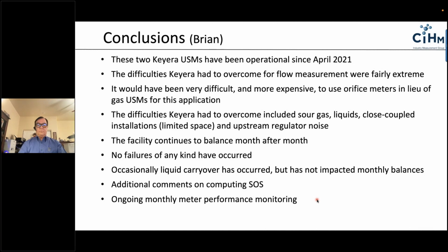So with this application, we had a lot of challenges to be able to measure this. We have slugging flows, we have liquids present in the gas, we got a bit of glycol carryover. The flow rates can fluctuate from 50 all the way up to 2,500. So a lot of different challenges, and where the piping spec is and the regulators are, without doing a major redesign of the facility, it made it very difficult. So we reached out to Strata Controls and RMG to see what solutions were out there, and they went above and beyond for us. This project came on very quickly because of a producer's needs, and we were 5 weeks basically from start to finish to get the metering tubes, pressure and temperature transmitters, and the RMG meters to site, with doing the calibrations at TCC and doing all the QA QC checks.